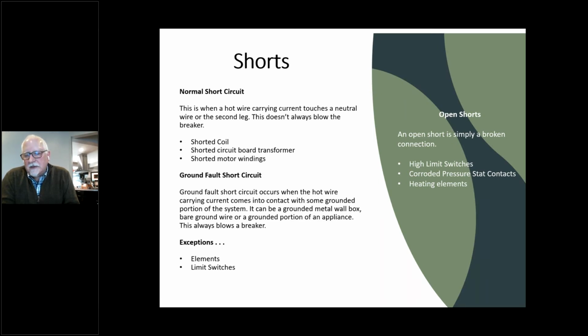The funny thing about elements, though, is that the actual wattage of the element will fluctuate a little bit when you feed it more voltage in terms of its power output. Can you repeat that? You're breaking up. The resistance of the element, the heat output of an element, will change a little bit with voltage. That's why some manufacturers list not just the wattage draw at one voltage. They'll provide a wattage draw over a range, depending on whether you're getting like 210 or 240 volts. But I figured that's a little more complicated than we need to be.